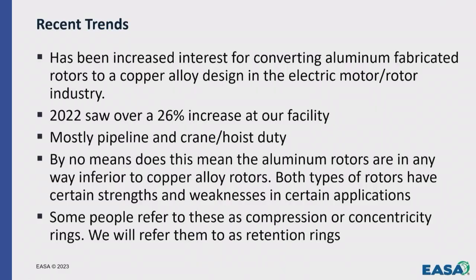But when you go with stainless steel retention rings, there's a couple things you have to think about. And first of all, just a couple clarifications on terms. When I say aluminum rotors, I don't mean your typical little die-cast rotors. I'm talking about the big fabricated aluminum type rotors where the rings and the bars are usually joined together by some type of aluminum rope weld. Lots of OEMs do it that way. And when I talk about a retention ring, I know in the industry some people call them compression rings, some people call them concentricity rings or just steel banding rings, but I'll be referring to them as retention ring, and a retention ring is any stainless steel ring we put over the copper shorting ring to help control expansion when the motor is running.